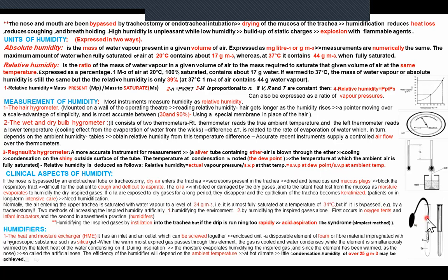At the level where condensation occurred, the dew point, I take it from special tables where I can estimate the saturated vapor pressure at the dew point. So instead of dividing both of these on each other, we will divide the saturated vapor pressure at the dew point over the saturated vapor pressure at the ambient temperature, the temperature where the instrument was being used.